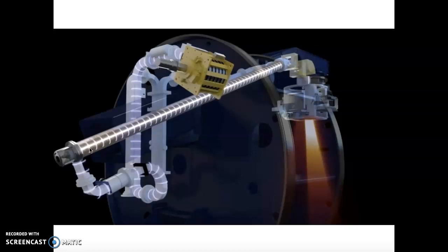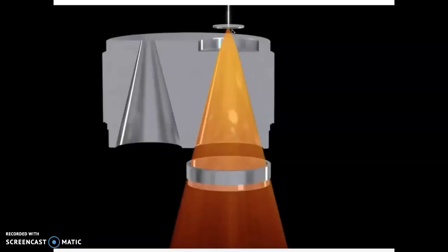And while it's going through the waveguide, the electrons are concentrated to a fine point, and that also occurs up here in the head of the linear accelerator. And these electrons are sped up almost to the speed of light until they hit this small cylindrical disc, which is also tungsten. Here you can see the electrons hitting the tungsten target, and this orange cone that you see is actually X-rays, radiation. So this cone obviously is too wide. It's going to affect healthy tissue, not just the tumor.